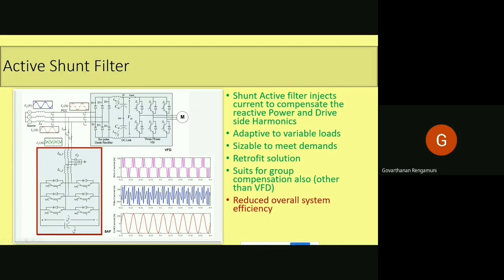It is a retrofit solution. So if there is a failure, we can remove this and put a new one. We need not disturb the variable frequency drive. It suits group compensation also. Not only VFD, if some other polluting load is connected, this active shunt filter is capable of mitigating those harmonics as well. Here we can see the only disadvantages: the reduced overall system efficiency, and if you are considering the overall cost compared to the passive shunt filter, the active shunt filter will be more expensive.